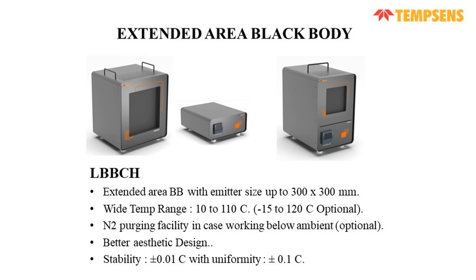Next, we have the extended area black body, LBBCH. The temperature range for this LBBCH model will be 10 to 110 degrees centigrade, and -15 to 120 degrees centigrade can be optional. The emitter size can be up to 300 by 300, like 50 by 50, 100 by 100, then 200 by 200, and then 300 by 300.